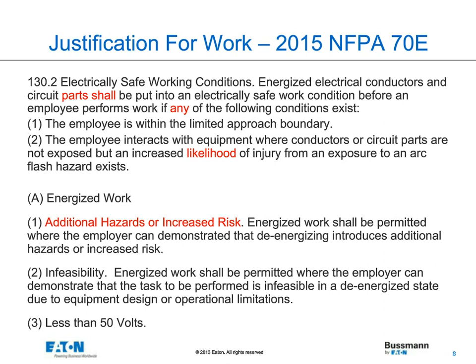If you look at these two reasons, the primary driver here is the infeasibility one. There are many cases when you are going to have a no hot work policy, but in order to verify the equipment is actually de-energized, you have to go in there. And during that process, you have to assume it's energized when doing the absence of voltage testing. So in many cases, even if you have a no hot work policy, you're going to have the arc flash hazard analysis or PPE per the tables that's suitable for that installation, even to just verify the absence of voltage.